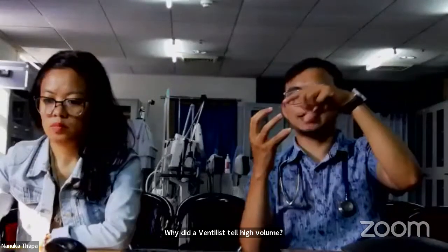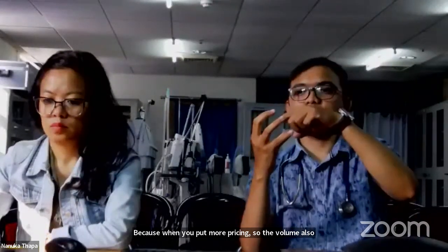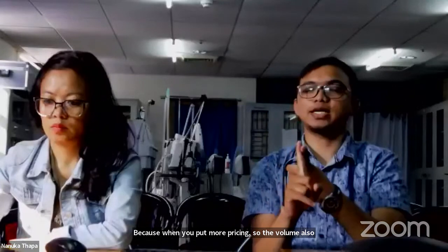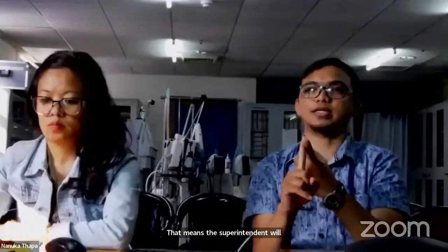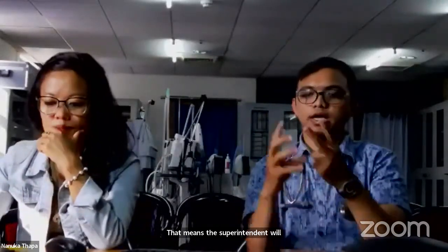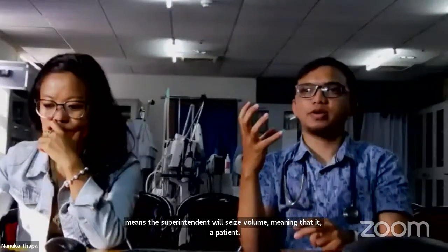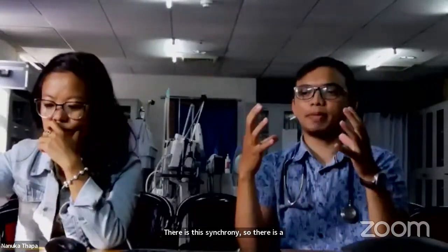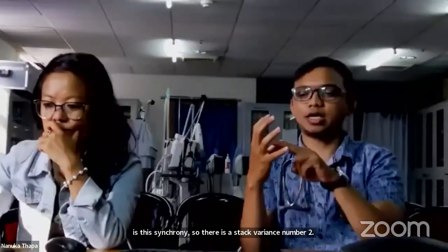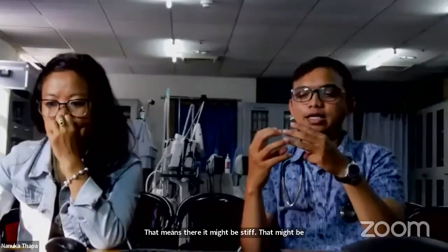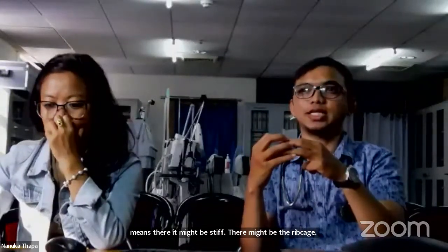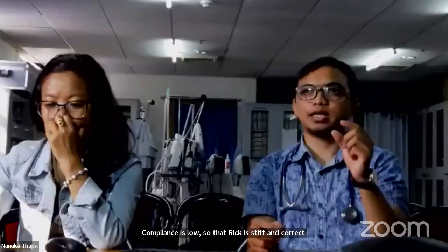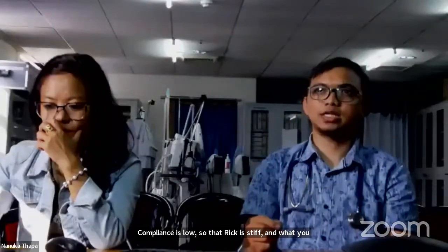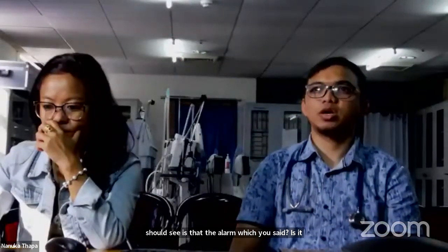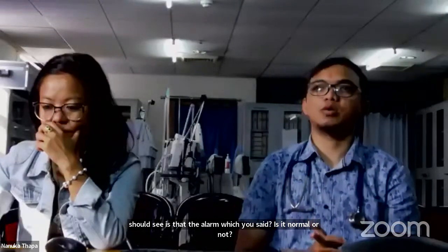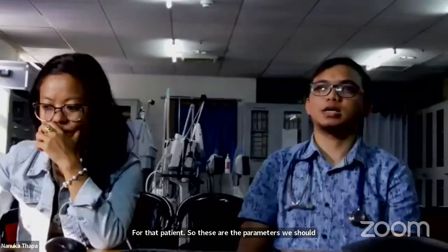In that way, the ventilator will sense volume, meaning that either the patient has dysynchrony, so there is stacking of breaths. Number two, the lungs might be stiff. There might be low rib cage compliance, so the rib cage is stiff. And third, you should see whether the alarm limit you set is normal or not for that patient. So these are the parameters you should check when the alarm goes off as high volume for that patient.